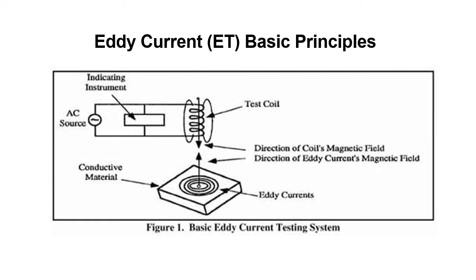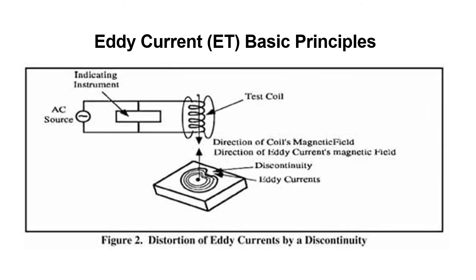This figure shows a surface probe as it is placed near the surface of a test article. The alternating magnetic field of the coil is essentially perpendicular to the face of the coil. The induced Eddy Current flows at a right angle to the magnetic fields. Therefore, the induced Eddy Current flow is parallel to the surface when the surface probe is held perpendicular to the surface. You can see that it sets up a secondary magnetic field created by the Eddy Current. And then, if you have a defect, it's going to disrupt that Eddy Current. Same setup, where we're inducing an Eddy Current into a material, but you can see where there's a discontinuity, so the secondary magnetic field created by the Eddy Current is disrupted. So that's what we're going to be able to detect.